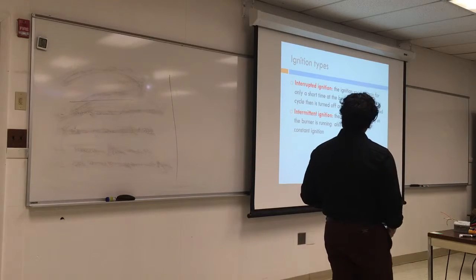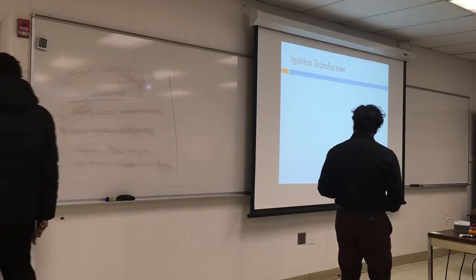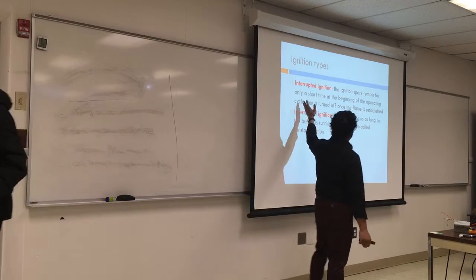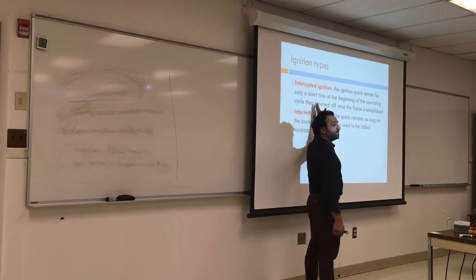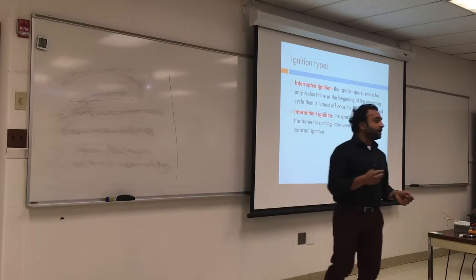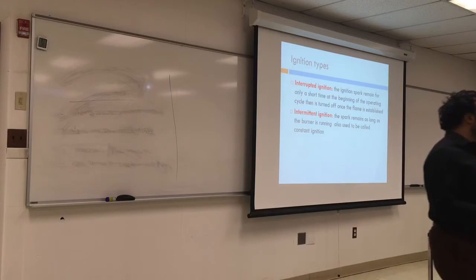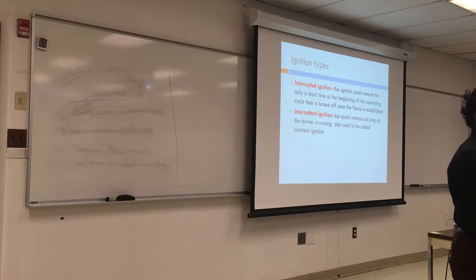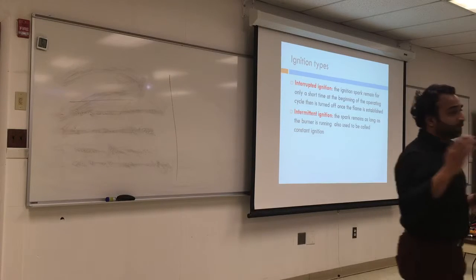If the spark is continuous, going all the time, that will consume energy. So let's focus on this a little bit. Interrupted ignition is the current code where you have to cut off the ignition once you prove the flame. How do you prove the flame? Cad cell. The cad cell sees the light, it will know there's flame, and it will cut off the ignition.